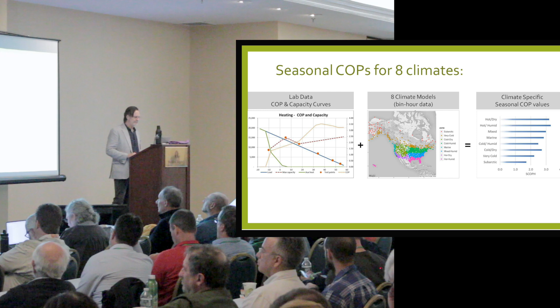So what we've learned from doing these load-based tests, we tested about 22 heat pumps over a period of 3 years, and not surprisingly, the results we got, which are on the right, are different from the AHRI ratings of these same units. On the right is the HSPF scale. These were all done before HSPF 2. On the left is the COP scale, but they are aligned, right? If the performance was the same, it would be a horizontal line.